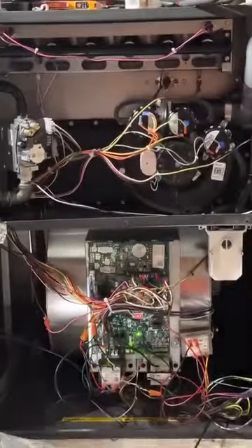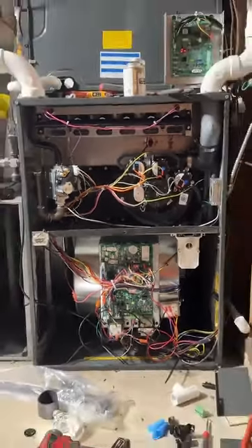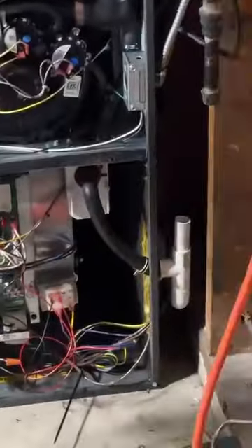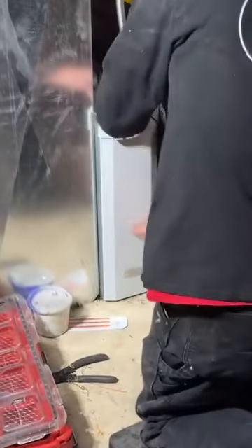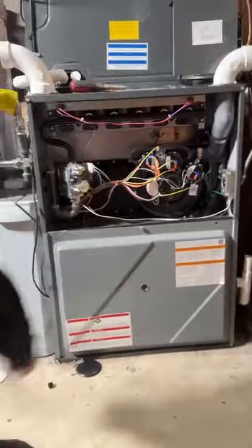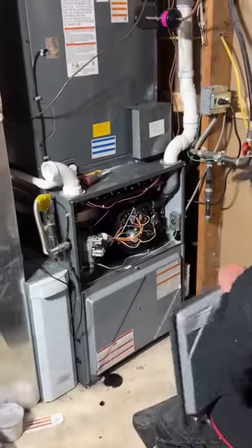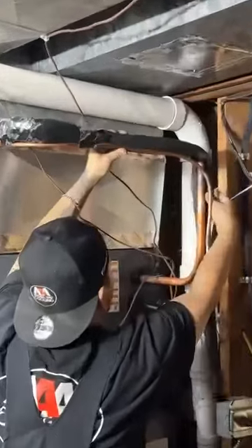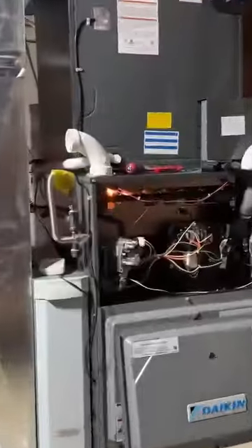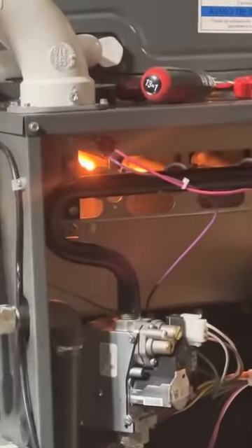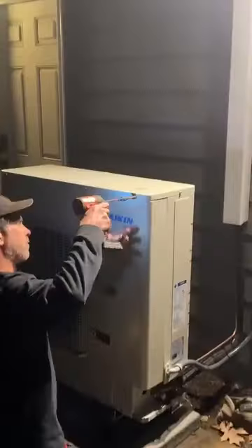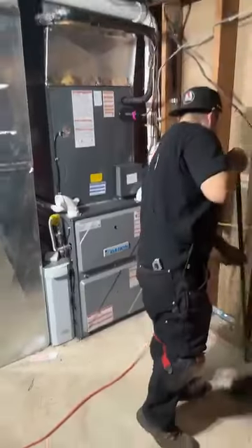Now with power back onto the system, the control boards come to life within the new unit. We also install a drain on the side of the furnace unit as well. Next, we install a new Aprilaire filter and begin to place the front panel covers back onto the front of the indoor units. We add some insulation with UV tape, and without a hitch, heat now engages within the new system. We place the front cover panels on the new outdoor heat pump system as well. We also installed a new thermostat for this customer. After a quick sweep and cleanup, this new installation is complete.